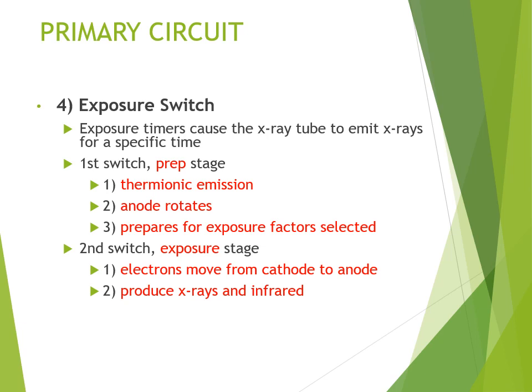We have the exposure switch, which is going to allow X-rays to be emitted for a specific time. The first switch is called the prep stage, during which we have thermionic emission, which is boiling off of electrons. The anode rotates, and it prepares for the exposure factor selected. In the second switch, we have the exposure stage, and that's where electrons move from the cathode to the anode. We produce X-rays and infrared radiation.